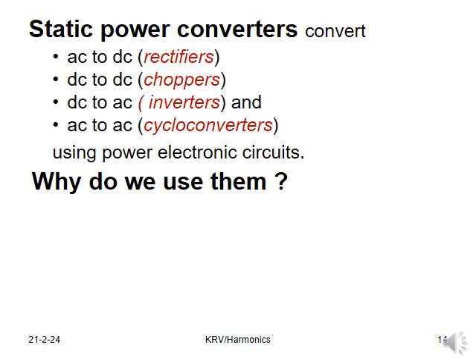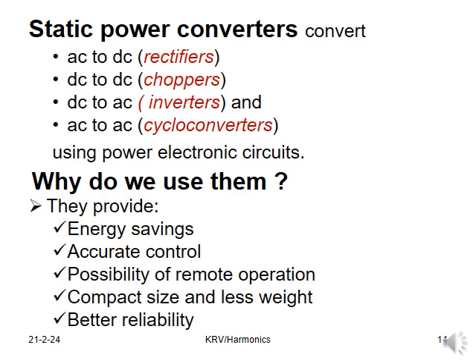When static power converters are non-linear and they produce current harmonics, why do we use them? The static power converters provide energy savings, which is the largest benefit of them. They are very accurate to control. There is a possibility of remote operation. They are compact in size and less weight. They offer better reliability.